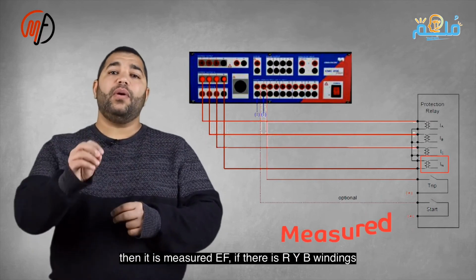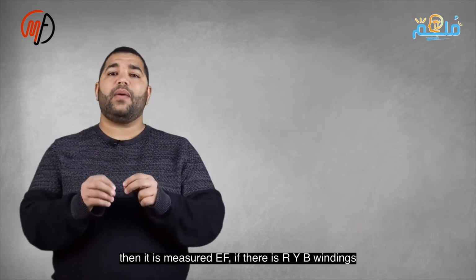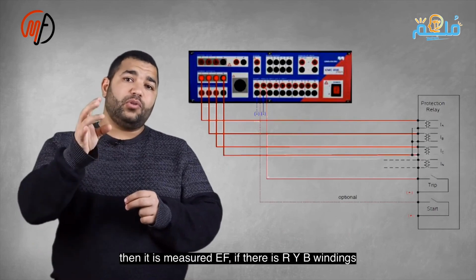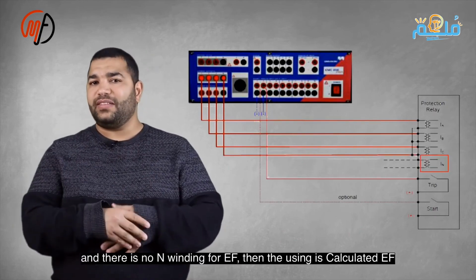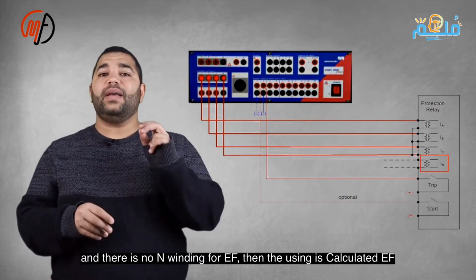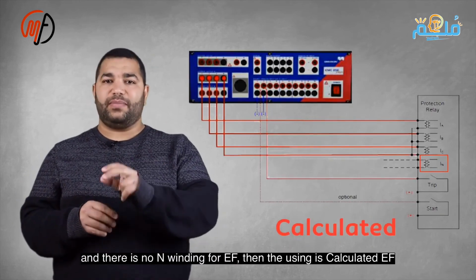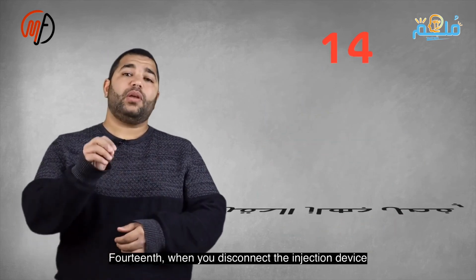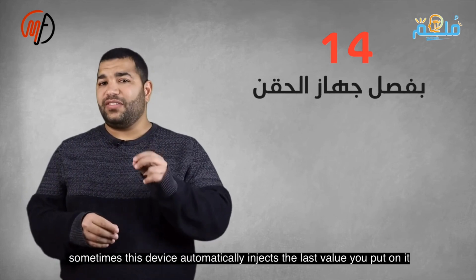However, if there are only 3 windings, red, yellow, and blue, and there is no winding for the earth fault or the neutral, use calculated earth fault. Disconnecting the injection device may cause it to inject the last set value, triggering the overcurrent relay. The issue is with the device, not the relay.